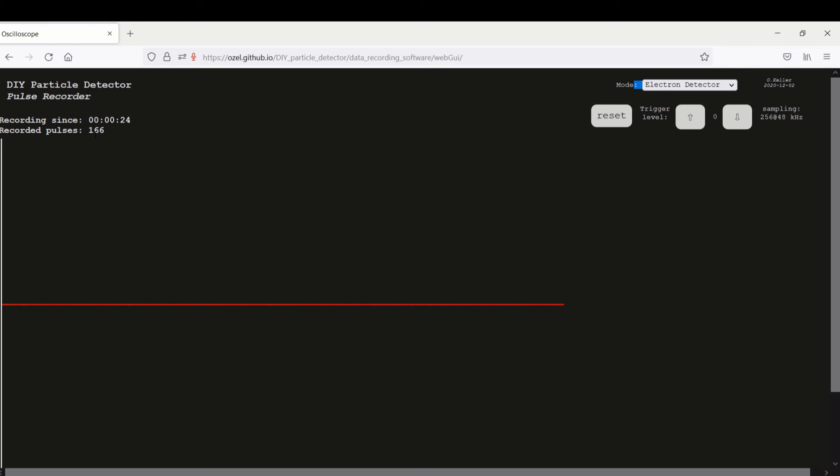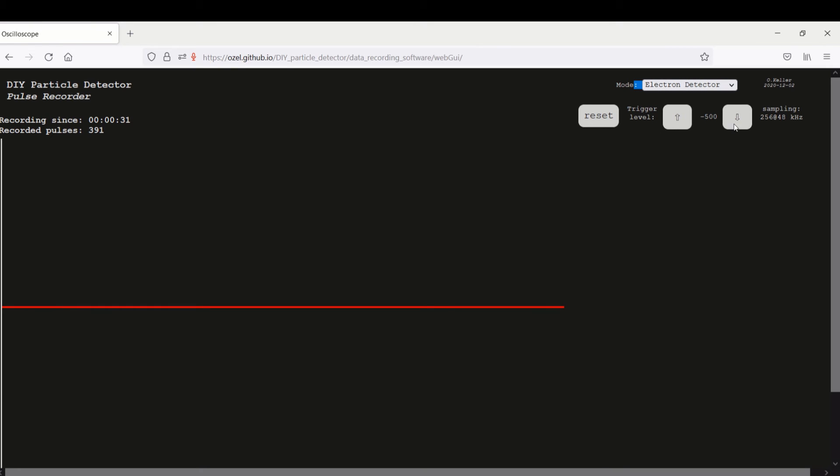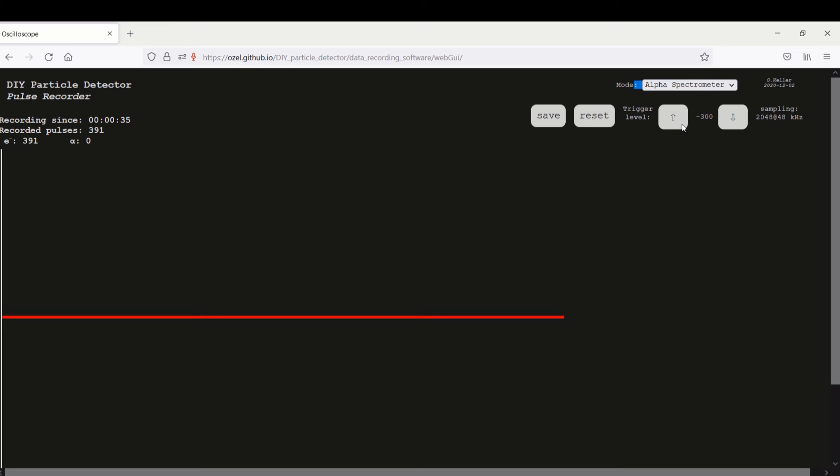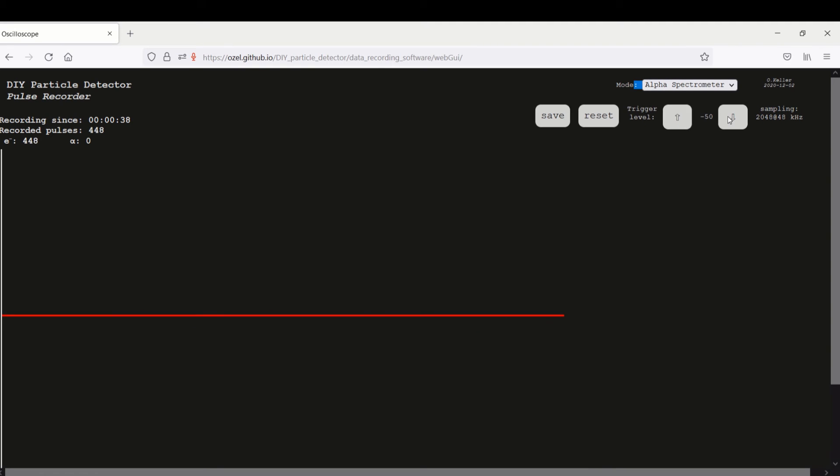If you have zero then it's counting already. For the electron detector version the minimum is minus 500. For the alpha spectrometer the minimum is minus 50. I will use the alpha spectrometer settings because I have a better minimum for first testing.